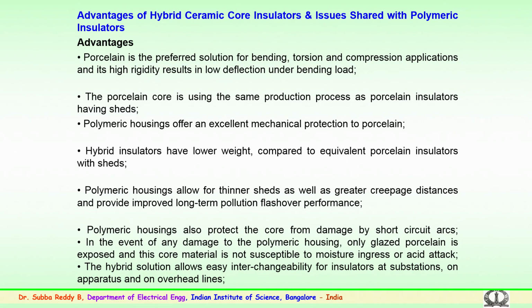Polymeric housings also protect the core from damage by short circuit arcs. This is one important aspect of a polymer housing. In case of any event or damage to the polymer housing, only glazed porcelain is exposed, and this core material is not susceptible to moisture ingress or acid attack. So several advantages are being shown here.